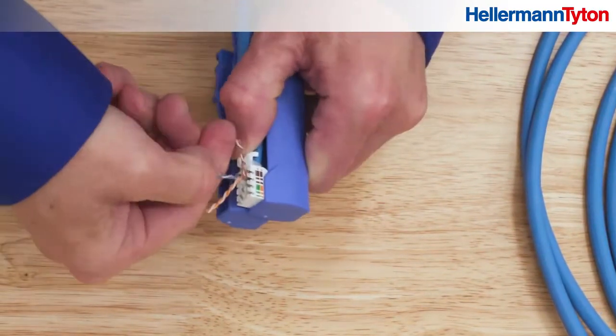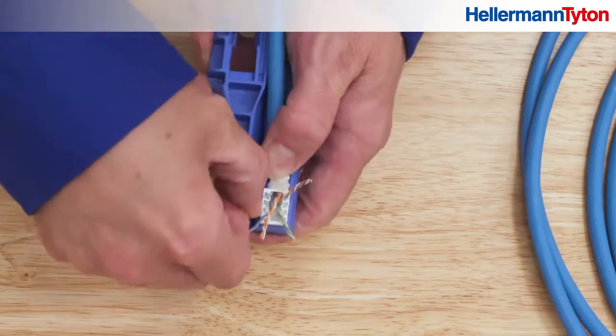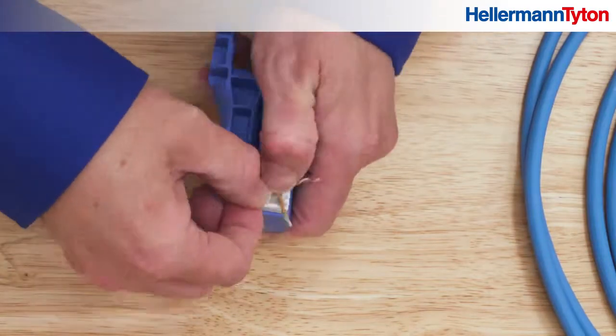Direct the wires into position. Untwist the pairs and lace each wire into the corresponding channel color. Note the manifold channels are angled to easily lace the wires. Place the remaining wires the same way.